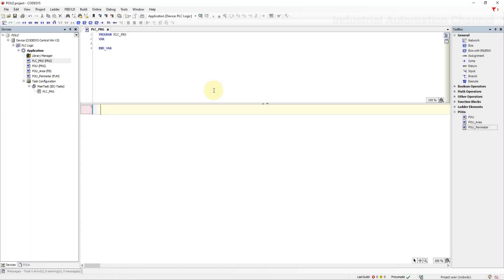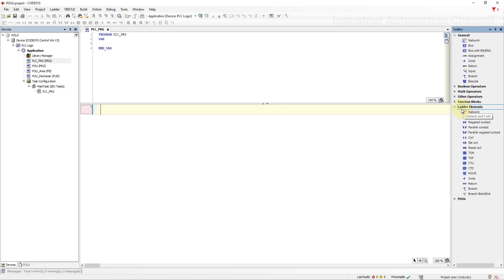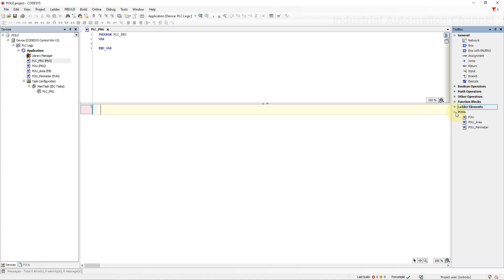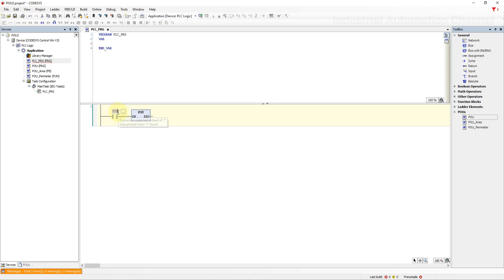With the ladder logic diagram, everything is the same. Just for calling a POU after you have created your program function or function block, a new category POU will appear under ladder elements. With drag and drop, you can call them. When enable is activated, the second program will be executed.